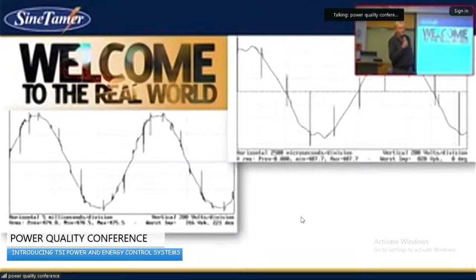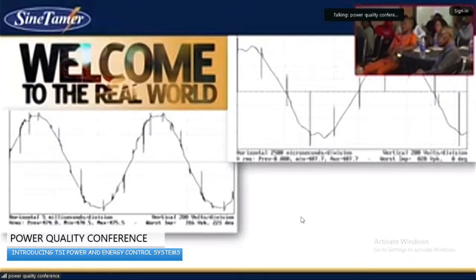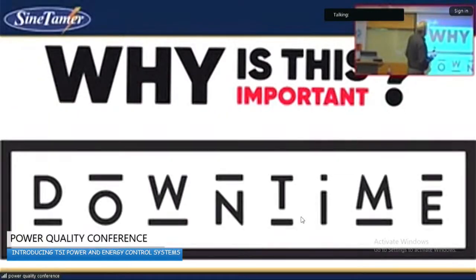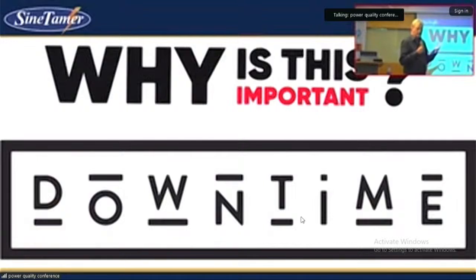Where that can be particularly damaging is at the zero crossing point. If you get one of these transients at the zero crossing point, and that goes through the rectifier into your electronics, it can confuse the logic. So instead of reading a 0, it's reading a 1. That can be the situation where the thing was working fine and now it's not, like I mentioned earlier. It can just be that little logical switch that causes the machine not to work anymore.